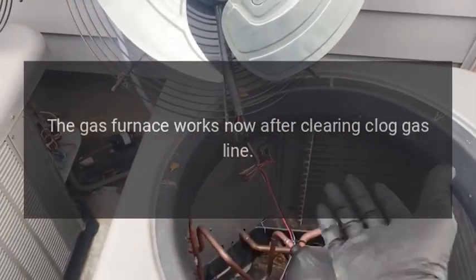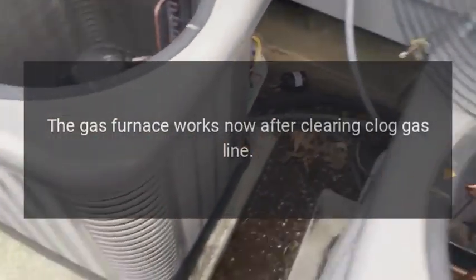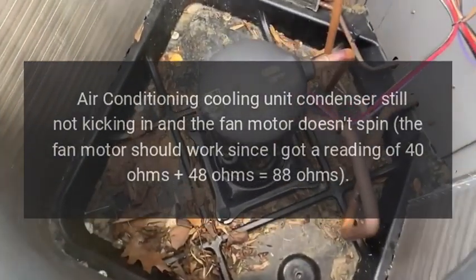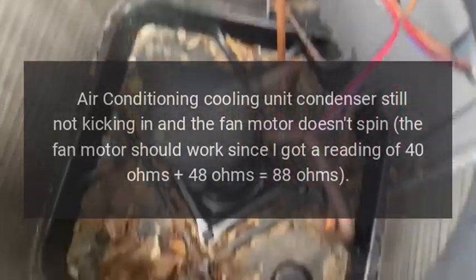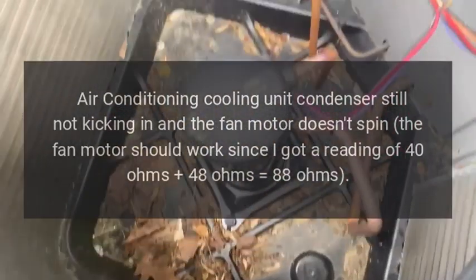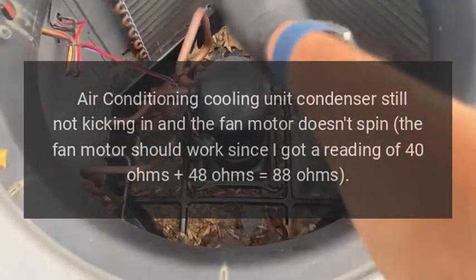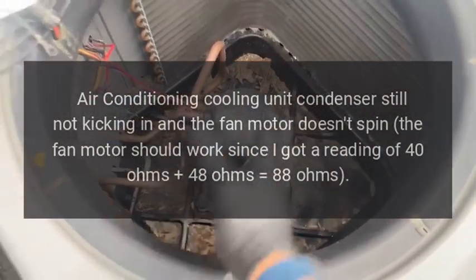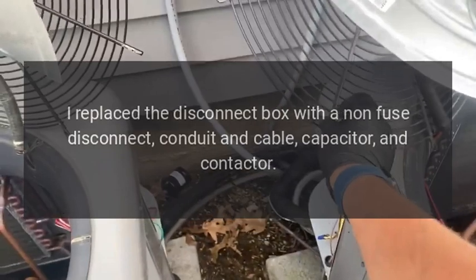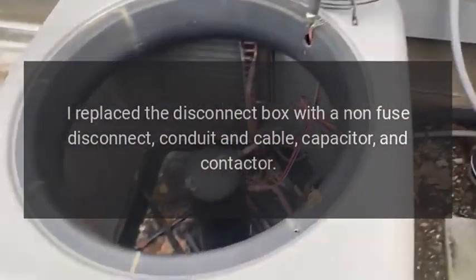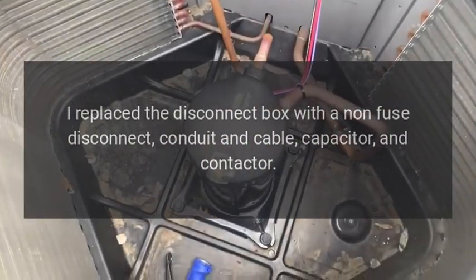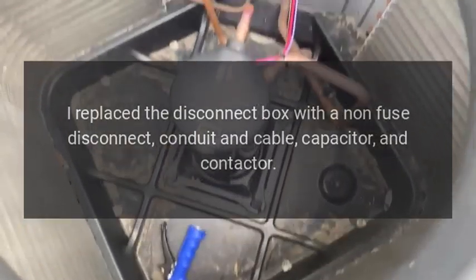The gas furnace works now after clearing a clogged gas line. The air conditioning cooling unit condenser is still not kicking in and the fan motor doesn't spin. The fan motor should work since I got a reading of 40 ohms, 48 ohms, 88 ohms. I replaced the disconnect box with a non-fuse disconnect, conduit and cable, capacitor, and contactor.